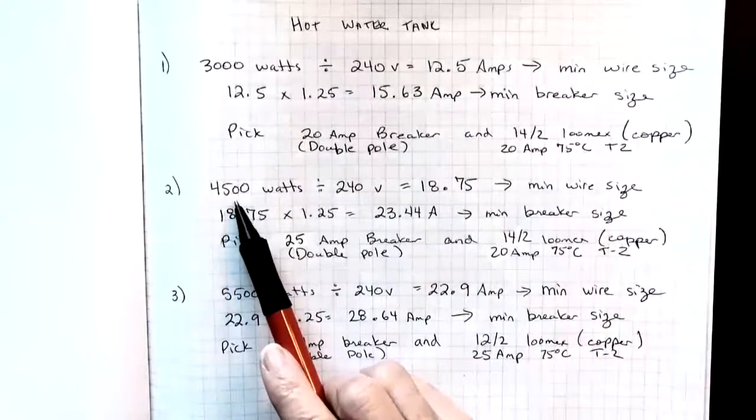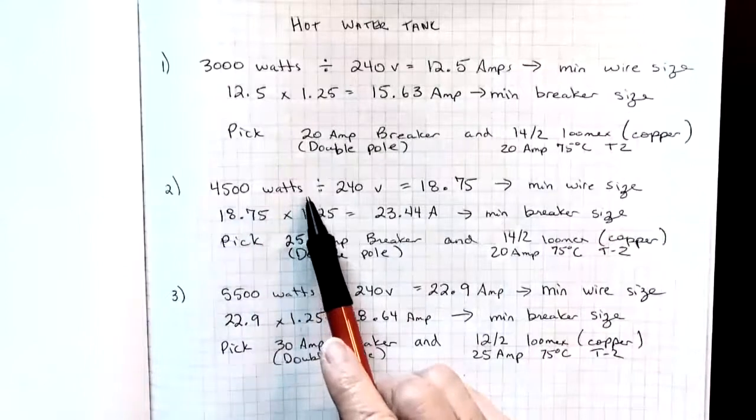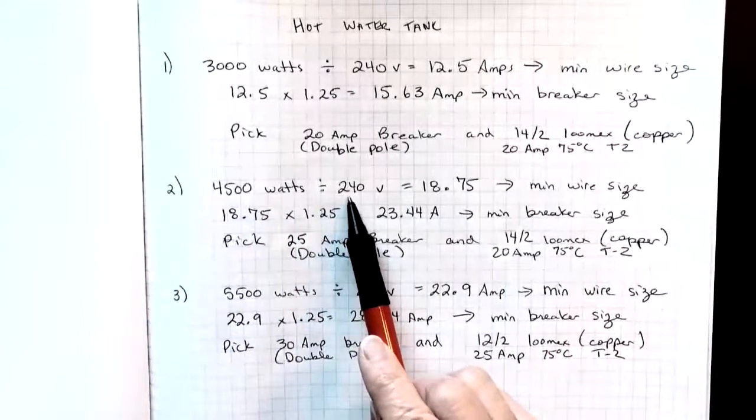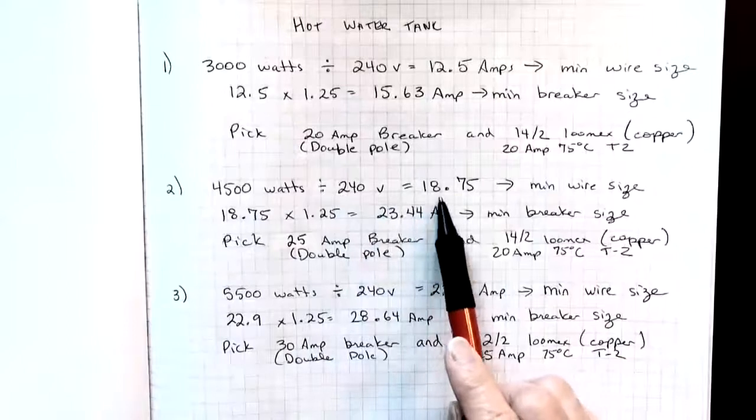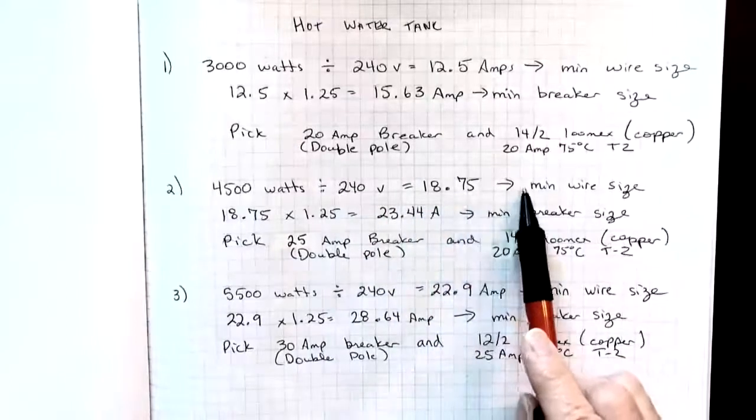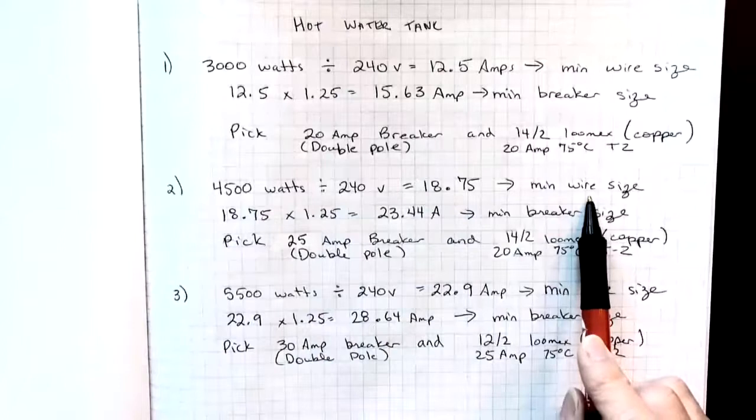Example number two is a 4500 watt hot water tank divided again by 240 volts. It gives us 18.75. That will be the minimum ampacity of our wire size.